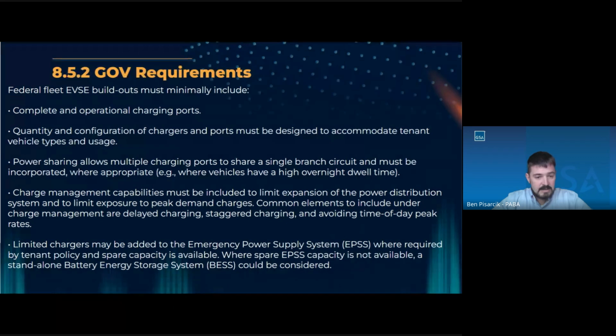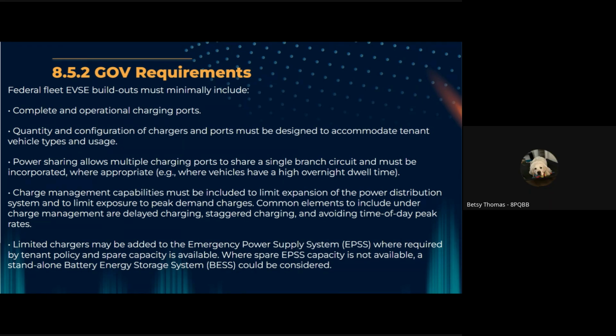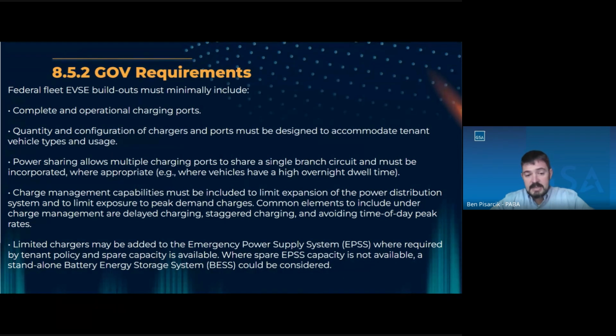Limited chargers may be added to the emergency generator or EPSS where required by tenant policy and spare capacity. Where spare EPSS capacity is not available, a standalone battery energy storage system could be considered and would be recommended. That could be charged via utility power in off hours, PV, that sort of thing. There are certain circumstances where it makes sense to have electric vehicles charged by a diesel generator, such as possibly an LPOE for an emergency vehicle, but it's not prevalent, I'll say.